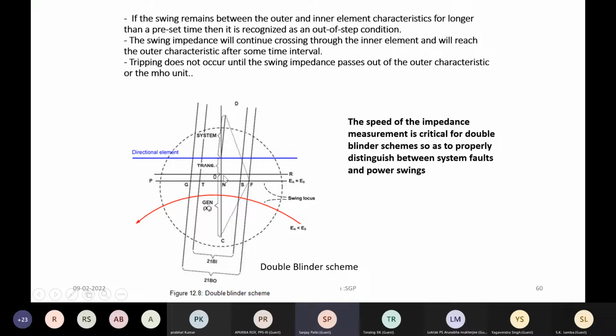So when the impedance locus actually comes to zone 1, electrically, power swing wise, you are almost 180 degrees apart between the system and the generator. So if you allow tripping to take place in zone 1, you are actually risking opening of the breaker when the two swinging voltages are in opposition, thereby chances of restrikes and pole failure will become more. So there is actually a greater risk of breaker failure when opening of the breaker is done in zone 1 during the power swing detected condition.